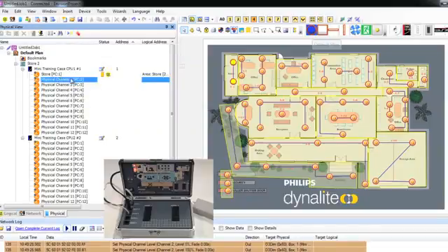Click auto flash. Look for the relevant lights flashing in your project, rename the channel to something logical, and then drag it over into the correct area and channel. Repeat for all of the channels on both of the load controllers. You'll notice that once you have assigned the physical channels to the logical areas, you'll see the status icon appear.